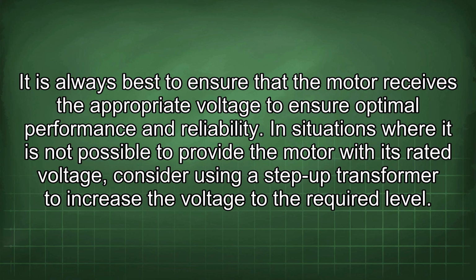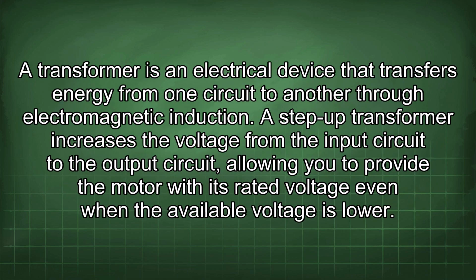In situations where it is not possible to provide the motor with its rated voltage, consider using a step-up transformer to increase the voltage to the required level. A transformer is an electrical device that transfers energy from one circuit to another through electromagnetic induction. A step-up transformer increases the voltage from the input circuit to the output circuit, allowing you to provide the motor with its rated voltage even when the available voltage is lower.